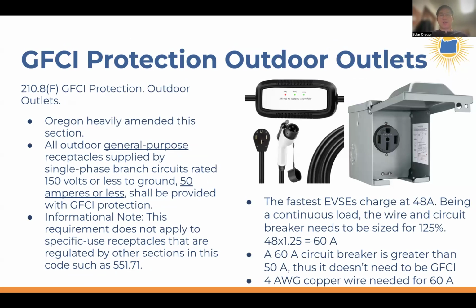Another place to think about GFCI protection is electric vehicle charging equipment. Under this requirement, if you plug a level one electric vehicle charger into a receptacle that could also be used for holiday lights or landscaping equipment, that's a general purpose receptacle, so it would need GFCI protection. But what about level two electric vehicle charging equipment? If it's above 50 amps for a branch circuit, it does not need GFCI protection.